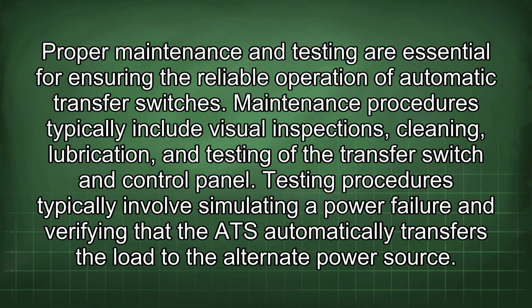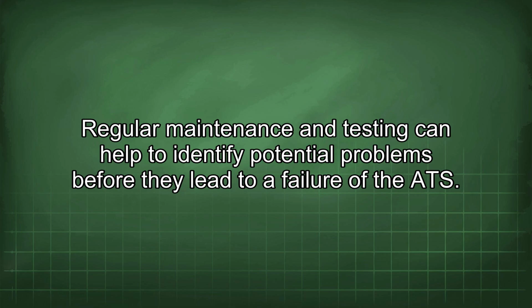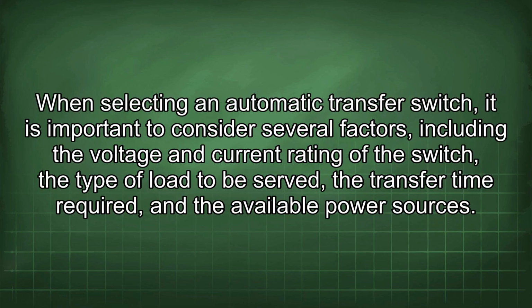Maintenance procedures typically include visual inspections, cleaning, lubrication, and testing of the transfer switch and control panel. Testing procedures typically involve simulating a power failure and verifying that the ATS automatically transfers the load to the alternate power source. Regular maintenance and testing can help to identify potential problems before they lead to a failure of the ATS. When selecting an automatic transfer switch, it is important to consider several factors, including the voltage and current rating of the switch, the type of load to be served, the transfer time required, and the available power sources.